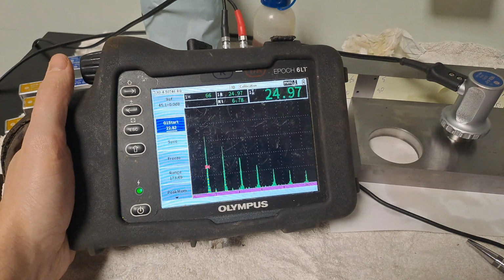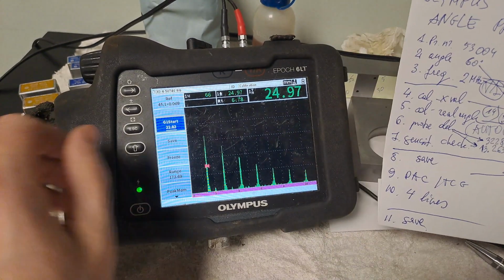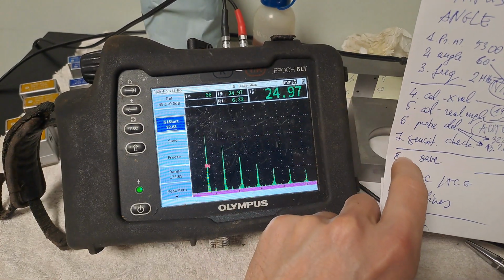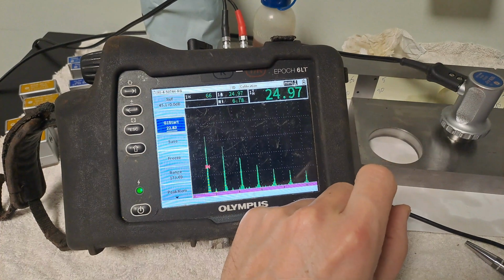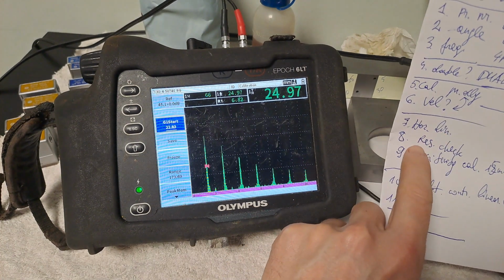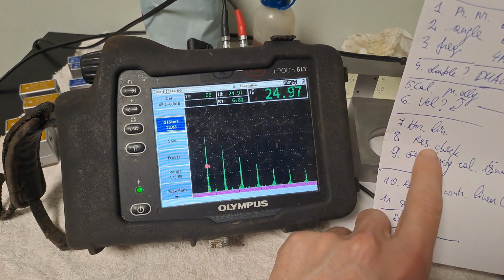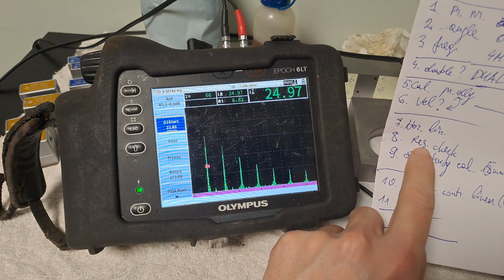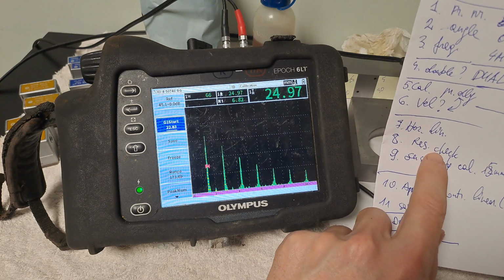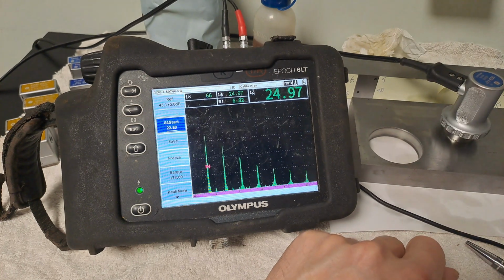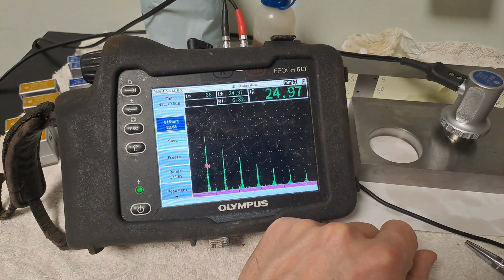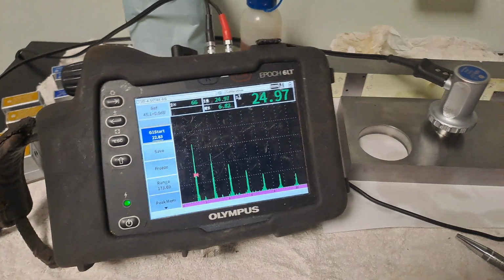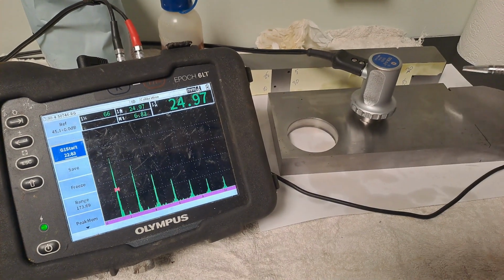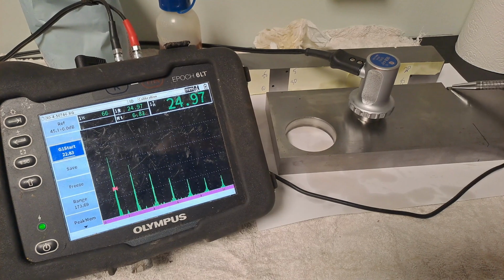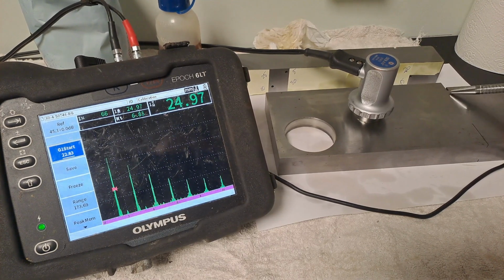So that's the what? The horizontal. No, not this one. Linearity, resolution check. I will save and we'll do the resolution check on the block on these. You cannot see. There it should be. We should see 3 spikes there.